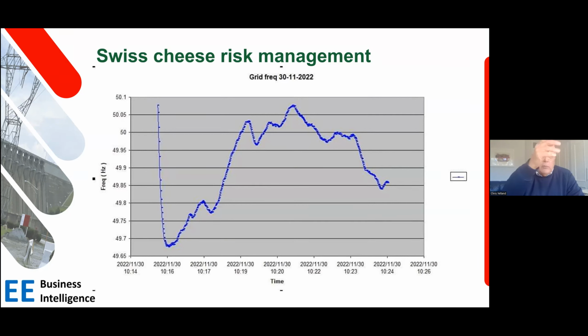And this is a control system at Eskom that you can see. As the frequency drops fast, the automation steps in and it recovers the frequency. It overshoots a little bit, and then there's an oscillation. So you can see how the automatic control system rapidly brought the frequency back to 50 hertz. It then oscillates a little bit because it's what is known as an undamped control system.